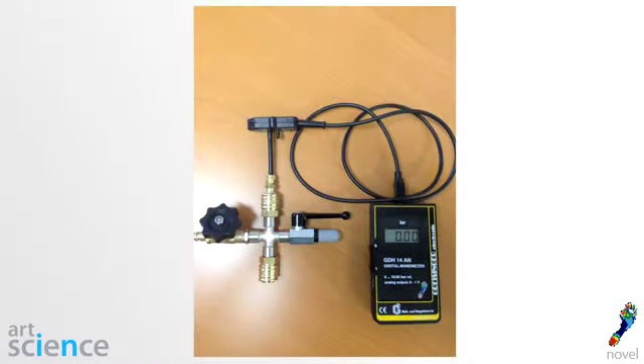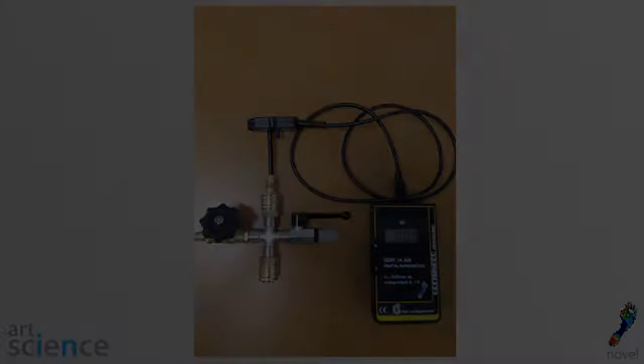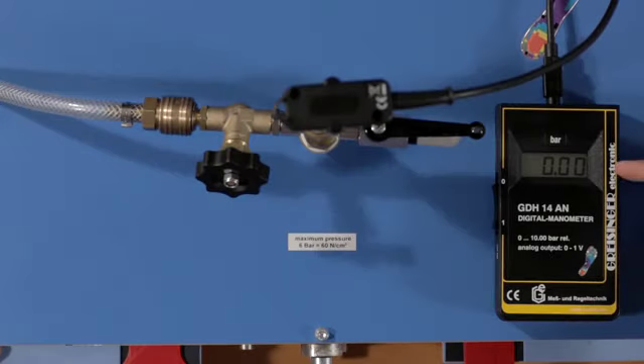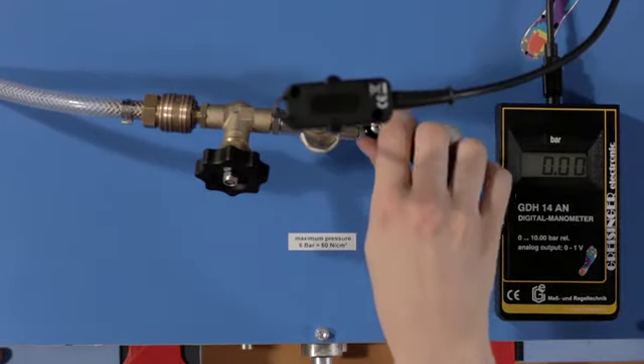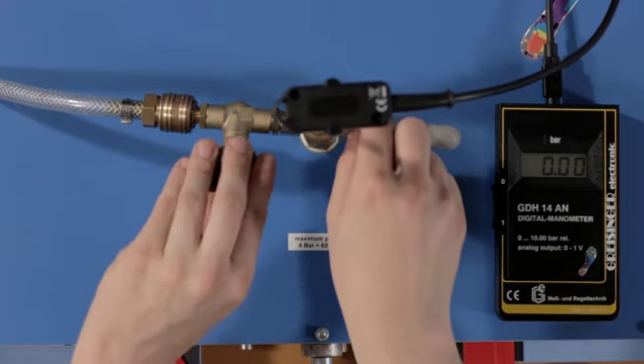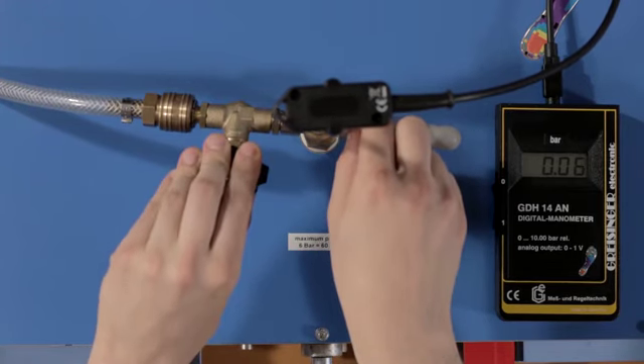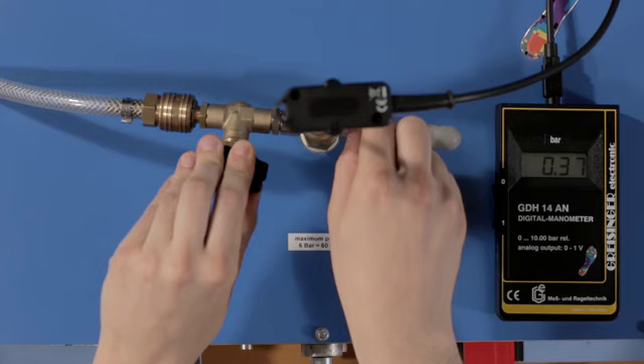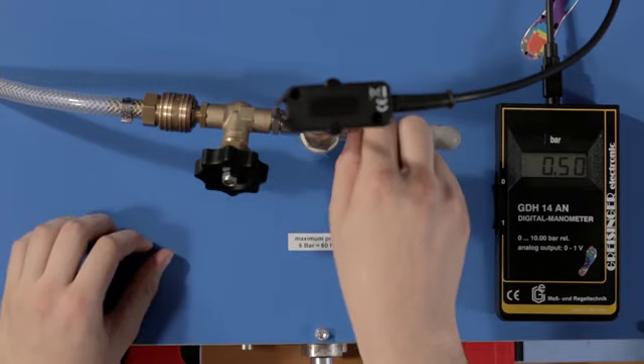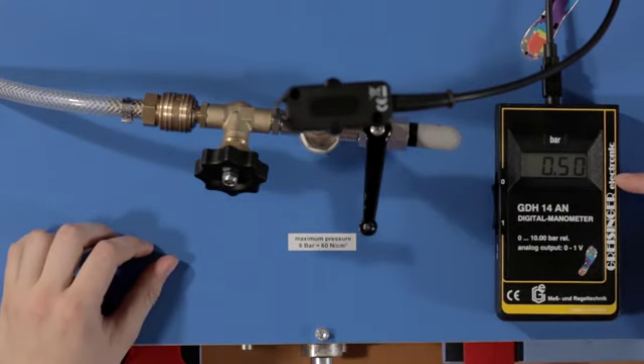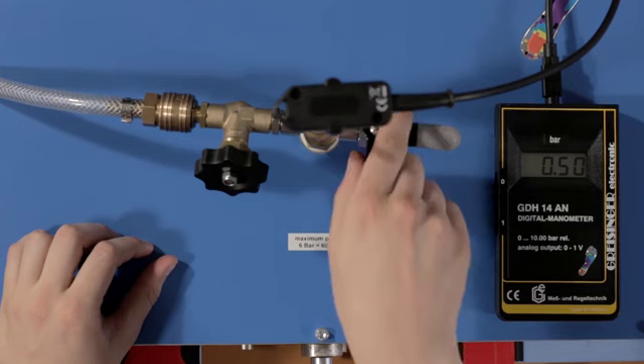Step 6. The T-assembly will be your tool in order to allow air to flow into the calibration device. When the outlet valve is parallel, air will flow out of the T-assembly and not build within the device. When it is perpendicular, the air from the air compressor will flow into the device. The manometer will measure the pressure and provide real-time pressure readings.